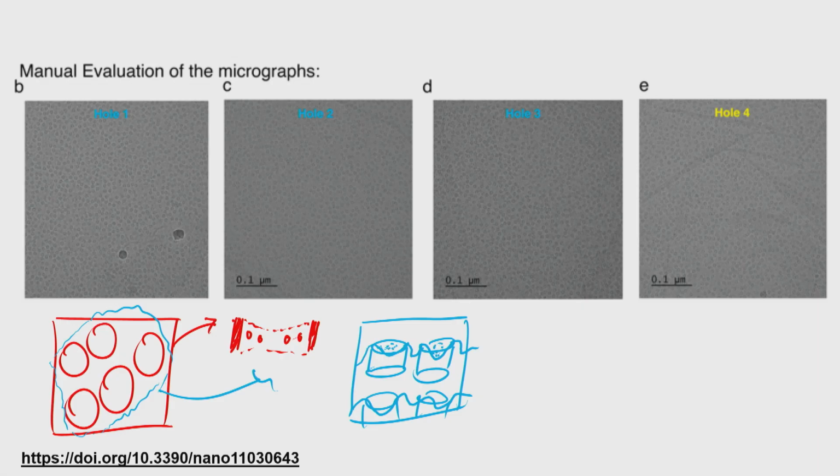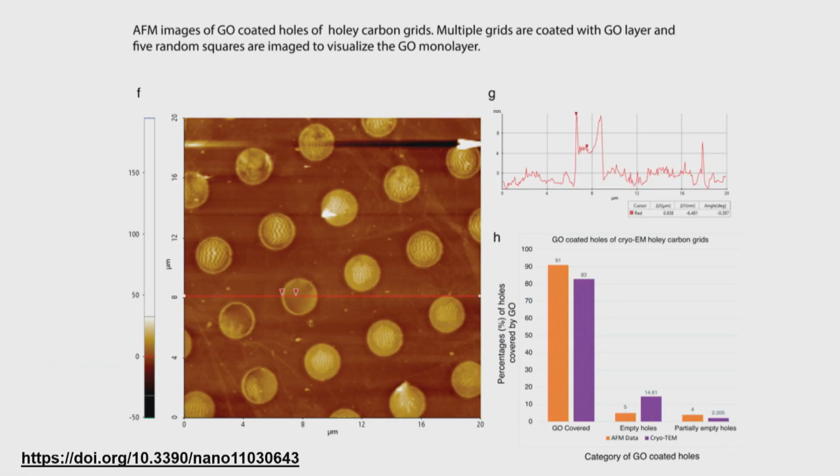If you add the sample, your sample will stay attached inside there. So there will be your sample, and it will be frozen hydrated, within the amorphous ice, but the amorphous ice thickness will be less because of this graphene oxide. But the graphene oxide layer will be there, and that will give you some kind of stability. So when the electron beam passes through this sample, the sample movement will be less. That is basically the main principle of using a graphene or graphene oxide coated grid.